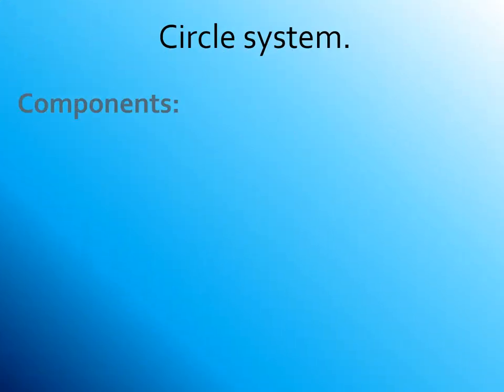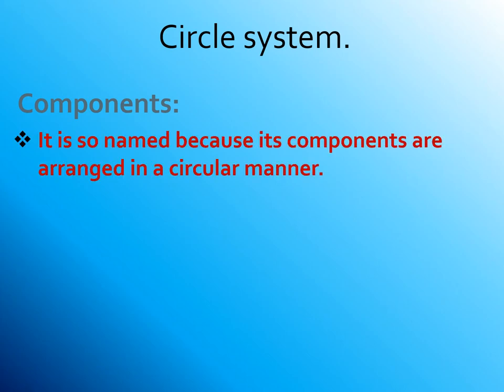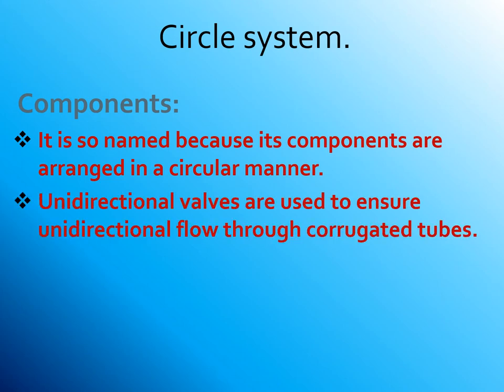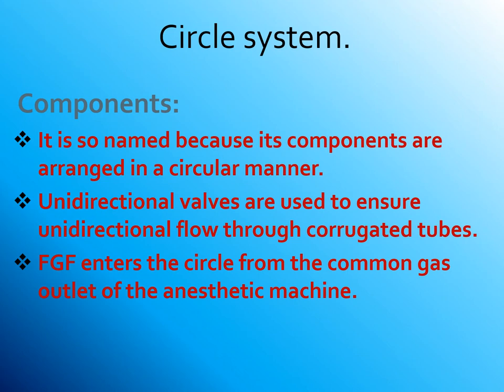Now we are going to talk about the circle system. It is so named because its components are arranged in a circular manner. Unidirectional valves are used to ensure unidirectional flow through corrugated tubes. Fresh gas flow enters the circuit from the common gas outlet of the anesthetic machine.